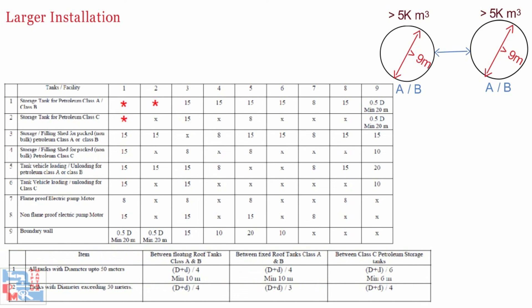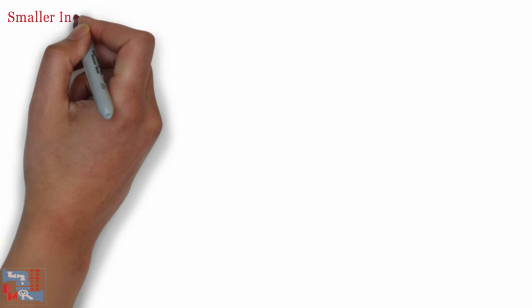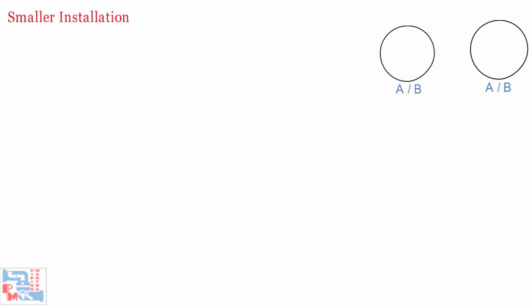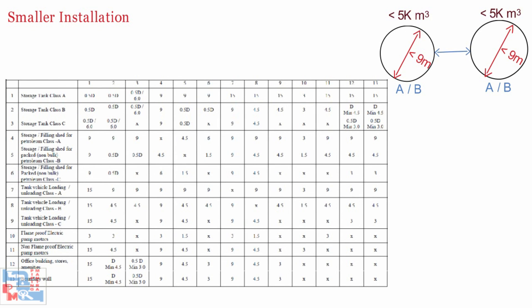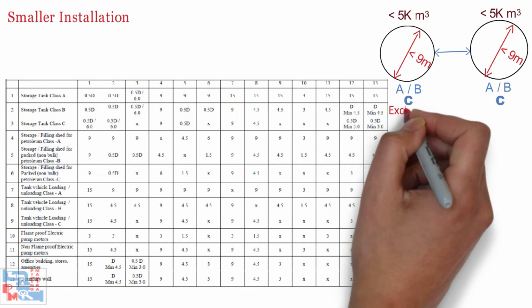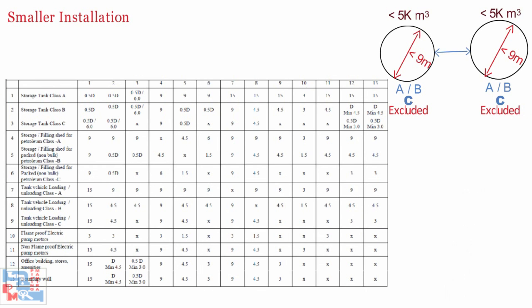Distances given in the tables are shell to shell within the same dike. In the table, X indicates suitable distances as per good engineering practices to meet construction, operational, and maintenance requirements. Where a star is marked, refer to the second table. For example, the separation distance between Class A or B floating roof tanks where the diameter is up to 50 meters should be D + d/4, or a minimum of 10 meters, where capital D is the bigger tank diameter and small d is the smaller tank diameter. These tables can be found in OISD 118. For smaller installations where total Class A and B storage capacity is less than 5,000 cubic meters and no tank exceeds 9 meters in diameter, a separate table applies for separation distances. This table also applies for Class C petroleum and excluded petroleum.